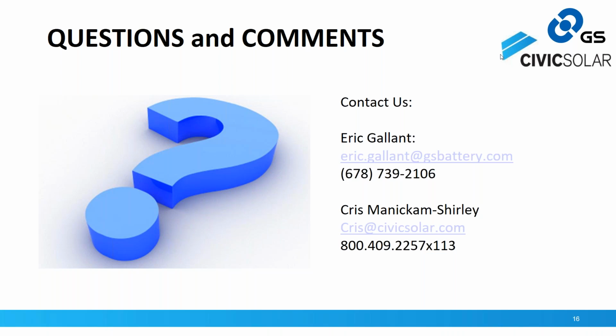So far our activities have been immediate response. We've deployed around 100 small-scale residential systems for customers with both grid-tied and no PV on site, and a lot of the immediate deployment has focused on these smaller residential systems. We've used a lot of GS batteries in 24-volt configuration—a standard AGM battery that gets 1,500 cycles at 50% discharge, which is great value and available. One of the hardest things for deployment in Puerto Rico right now has just been product availability; we've seen a lot of systems get pushed back because the products aren't completely there for deployment.